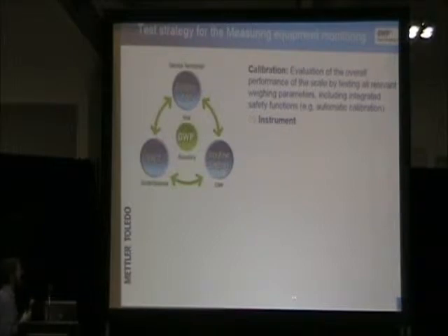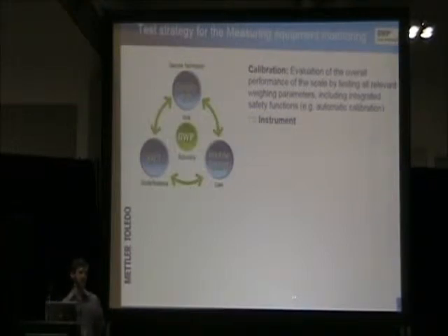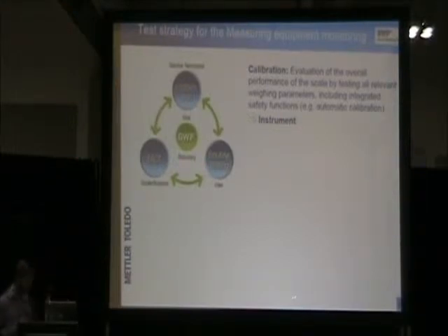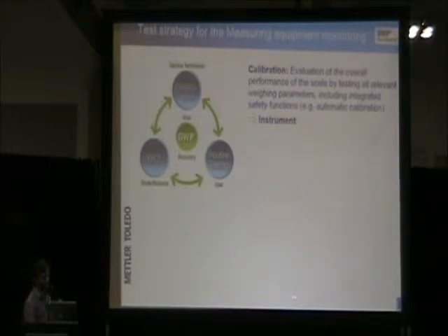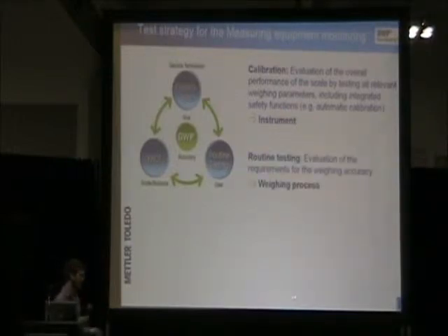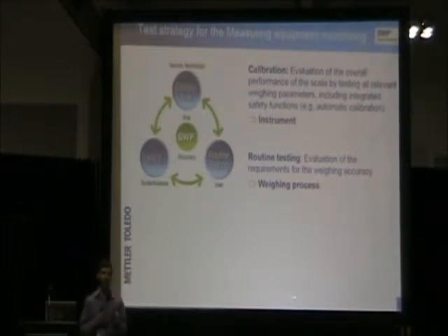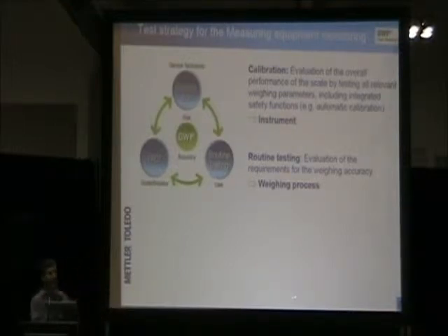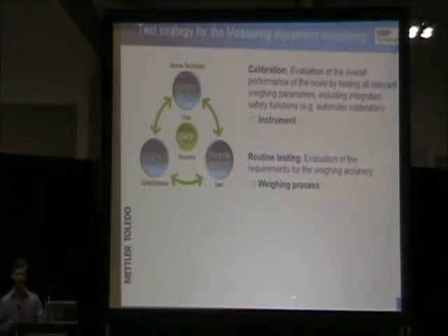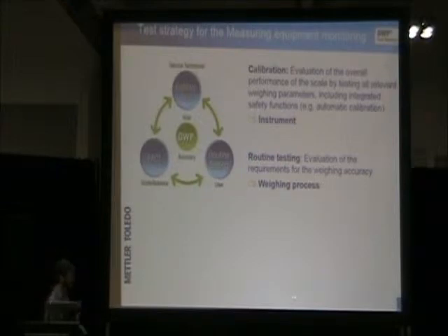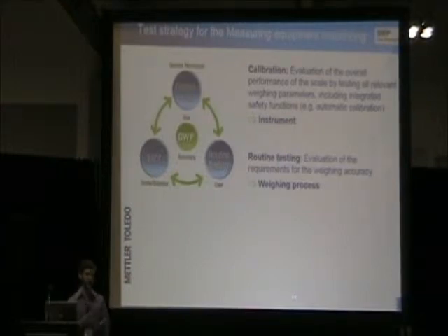When it comes to calibration, that is the evaluation of the overall performance of the balance or scale that is achieved by testing all of the different parameters that I mentioned prior: sensitivity, linearity, non-linearity, eccentricity, etc. Routine testing would be when you're doing your daily spot checks. You take a calibration weight and put it on your instrument, and that calibration weight has a certificate of traceability, and you see what that weight value is compared to the certificate and if it's within the tolerance that you're trying to achieve. You can also perform repeatability tests, which would be doing replicate weighings with the same mass, taking a standard deviation to see if that repeatability is within your tolerance.